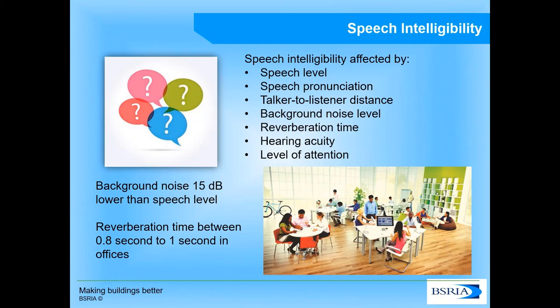Speech intelligibility is how easy it is to understand someone talking to you. It is affected by speech level, pronunciation, distance between people, background noise levels, reverberation time, hearing acuity, and level of attention. A basic rule is that background noise should be at least 15 decibels lower than the speech level. Reverberation time should be between 0.8 and 1 second in office spaces to aid speech intelligibility — too echoey and you struggle to understand speech, but too little reverberation can also stop sound from propagating.